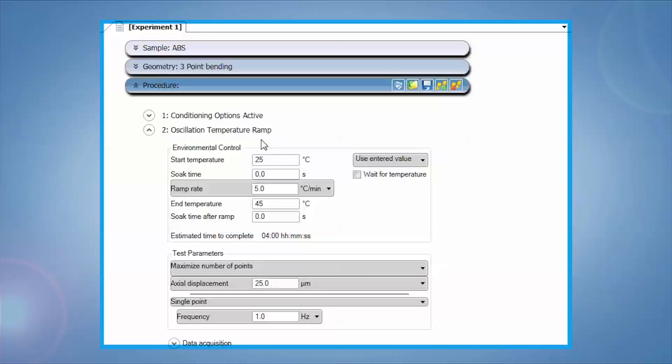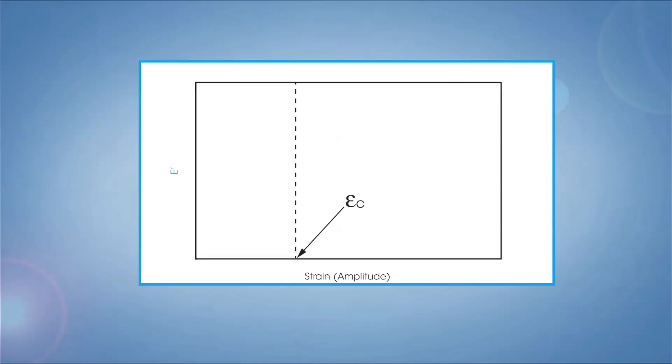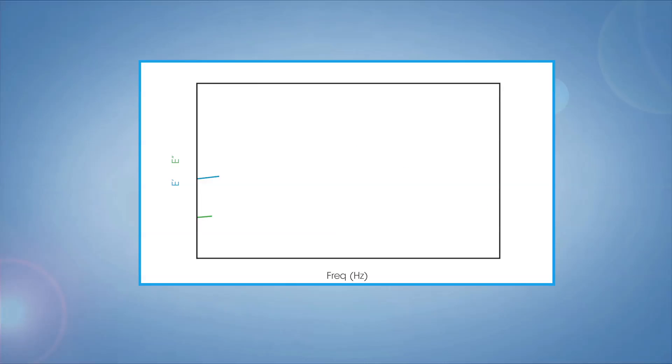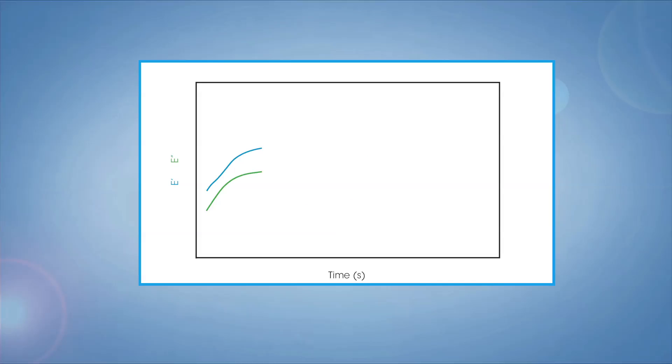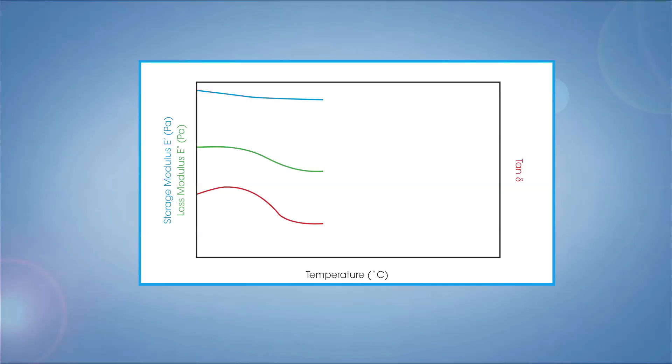This oscillation step can include an amplitude sweep to determine the linear viscoelastic region, a frequency sweep for viscoelastic characterization, a time sweep to determine stability, or a temperature ramp or sweep to measure thermal transitions in modulus as a function of temperature.